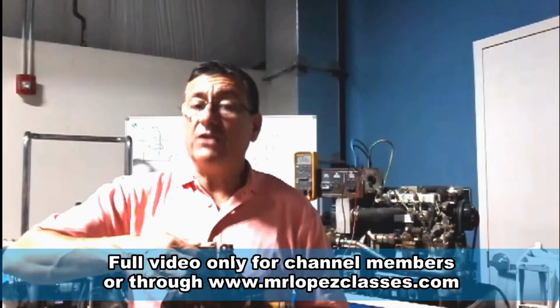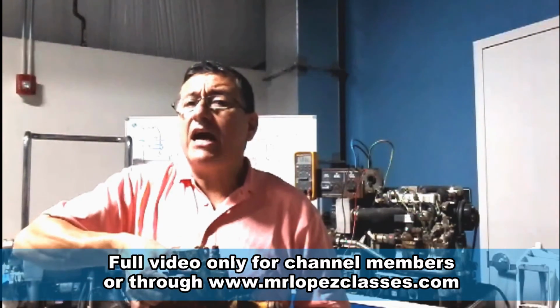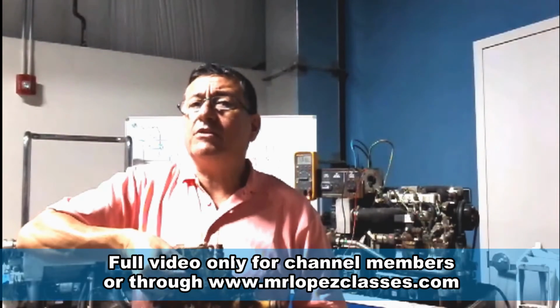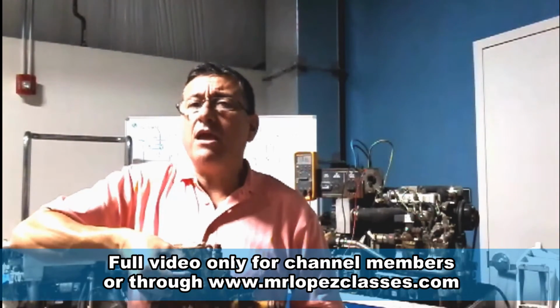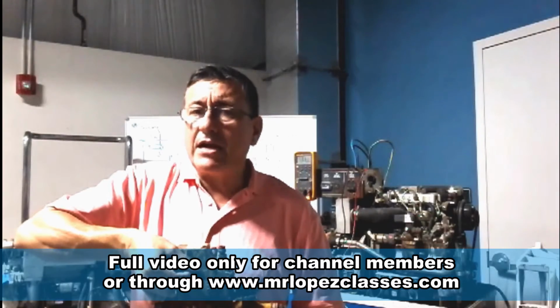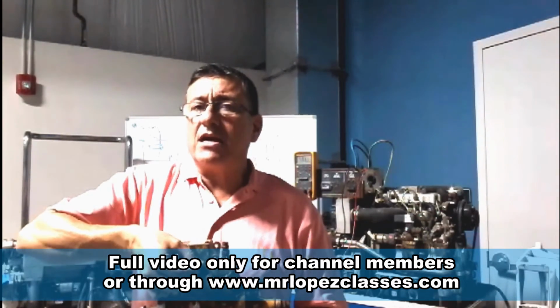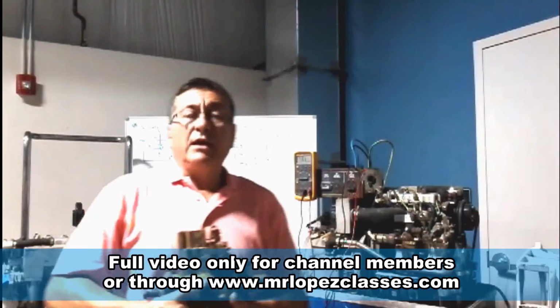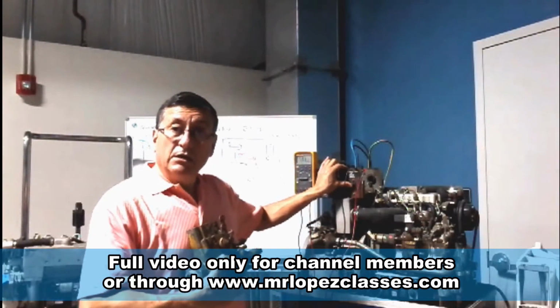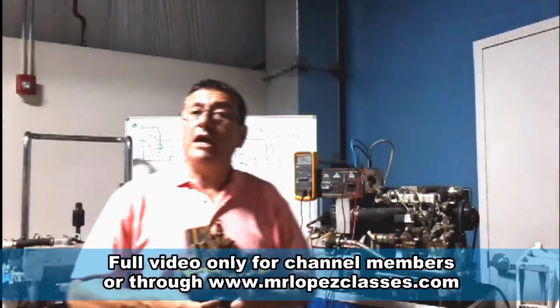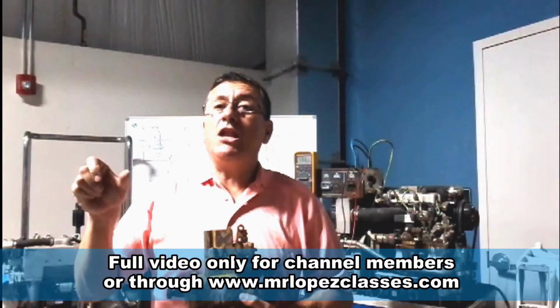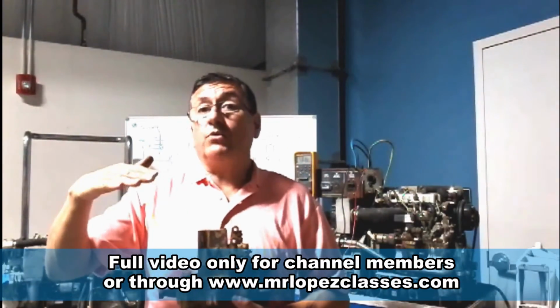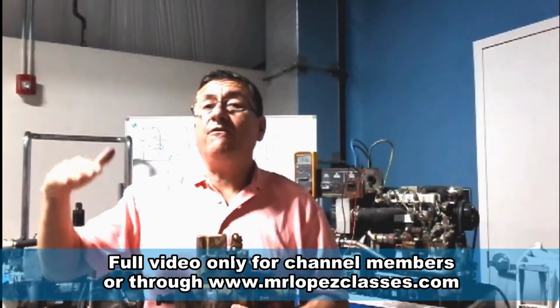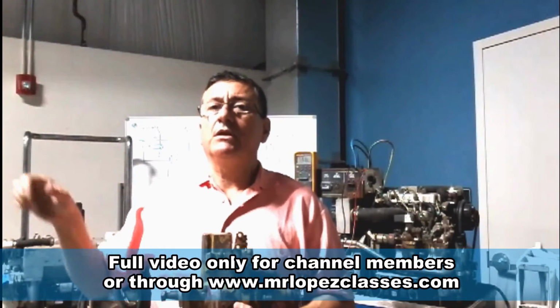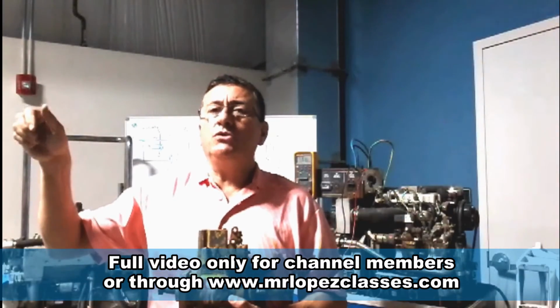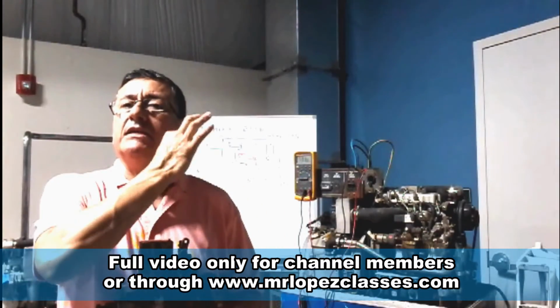I cut this safety wire and I adjust the idle bolt until the frequency increases: 58, 59, 60 Hz. And now, with 60 Hz, I go into the AC panel. I turn on the breaker again. Once again, breaker on, go to the AC panel, and I apply loads slowly. I start with the small loads and I finish with the heavy loads, air conditioning equipment. I apply the loads and I check that the frequency stays at 60 Hz.